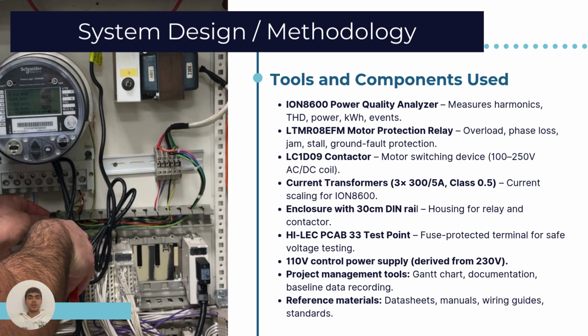Yep, so let's jump right into the tools and components used, which I've already mentioned before. The ION 8600, which is the most important component in this project. It measures harmonics, THD, power, kilowatt hours, events, and even those faults that can be detected through the motor protection relay, the relay which acts like the brain of the system and decides which faults to trip. And once a fault occurs, the LC1D09 contactor will open the circuit, which turns off the motor.